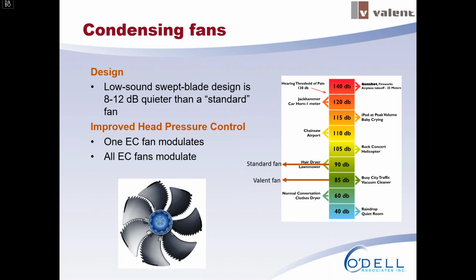So a standard paddle condenser fan, you'll see on that chart there is right around 90 decibels, somewhere between a hairdryer and a lawnmower, quite loud. The condenser fan that Valent uses is about 8 to 12 decibels quieter, which is pretty significant. So we provide lower sound fans, and then operationally we also offer more ideal control of those fans. So I'll talk about these options in the subsequent slides here. But just to spoil it, we have one EC fan modulating, so that's an option. Or you could have all of the condenser fans modulate together, and we'll talk about the advantages of those.